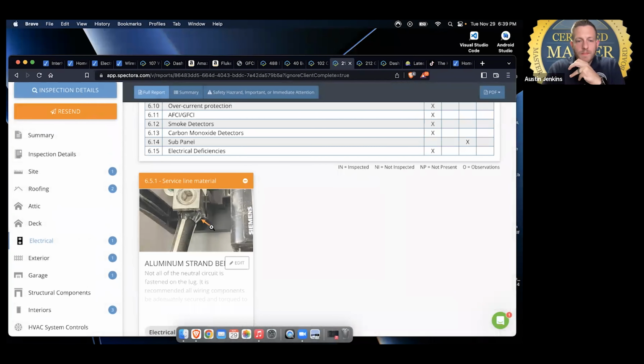Moving on to the next one — this was a brand new construction home just finished two months ago. Here's the neutral wire, which didn't have all of the aluminum strands under the lug. I have to write that up because, even though this passed inspection by the deputy state electrical inspector, each strand of that aluminum wire is there for a reason, so they all need to be under the lug.